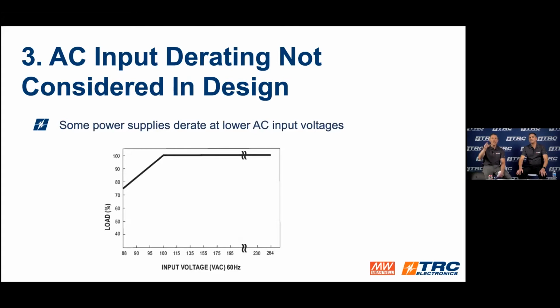Mike, why does this happen in some power supplies, but not all? Sure. Typically power supplies are designed to operate at 100 volts VAC, which seems to be the low line standard for North America. But what could happen is as you get into a brownout condition in certain applications, especially in the summertime, where the grid voltage can dip below 100 volts...